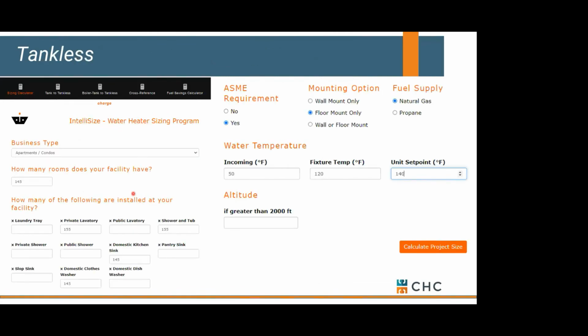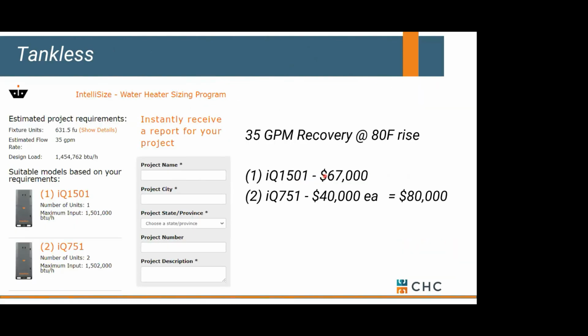Let's look at tankless. Okay, what's unique about tankless, at least with IntelliHot, the set point doesn't matter as much as the fixture temperatures do. Okay, so this one's critical. Obviously, incoming and fixture temperatures are driving the selection. In this case, we need 35 gallons of hot water. It's going to equate to about 1.5 million BTUs, or in our case, an IQ1501, which is about $67,000 to go tankless. No storage tank.